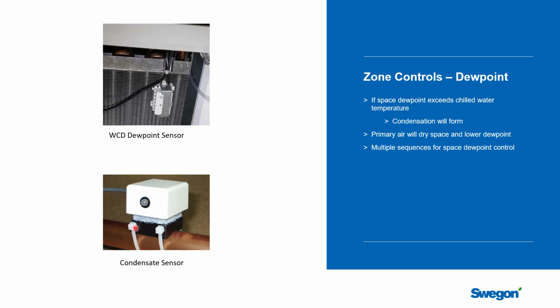And if any water starts to form on this pipe, the sensor will pick that up and let the building automation system know that the condensation is starting to form. So the top one allows you to be more proactive. As you get close to your dew point, you can start looking at strategies to manage the fact that you're getting very close to dew point, which is when condensation starts to form.